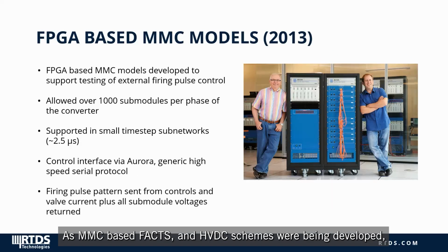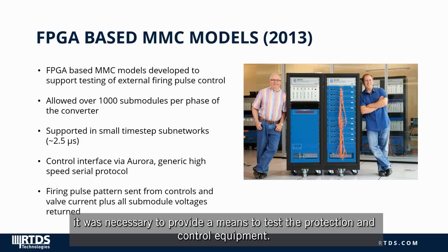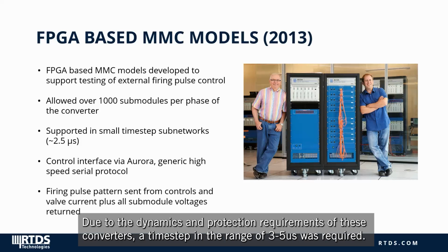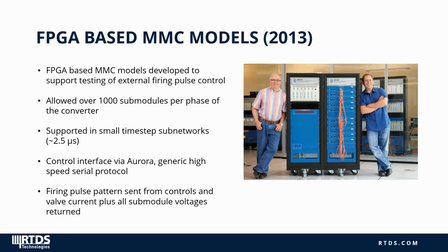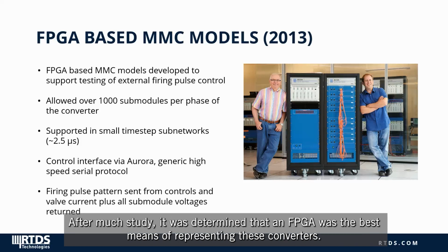As MMC-based FACTS and HVDC schemes were being developed, it was necessary to provide a means to test the protection and control equipment. Due to the dynamics and protection requirements of these converters, a time step in the range of 3 to 5 microseconds was required. After much study, it was determined that an FPGA was the best means of representing these converters.